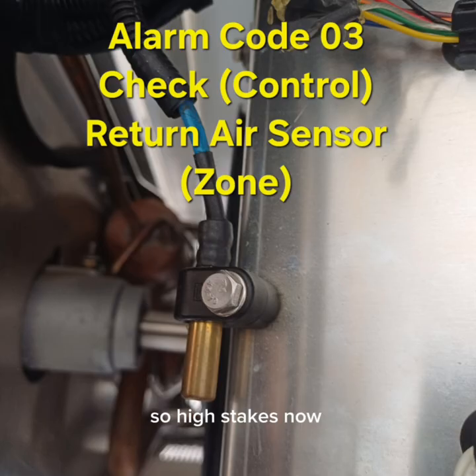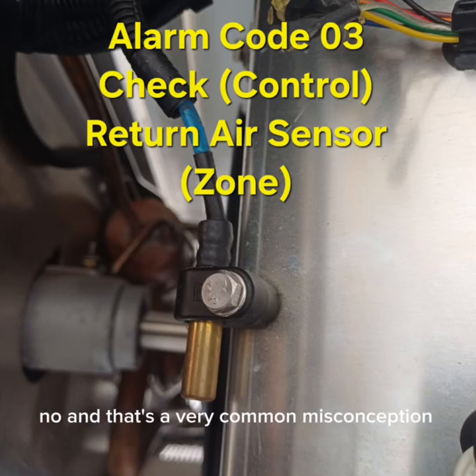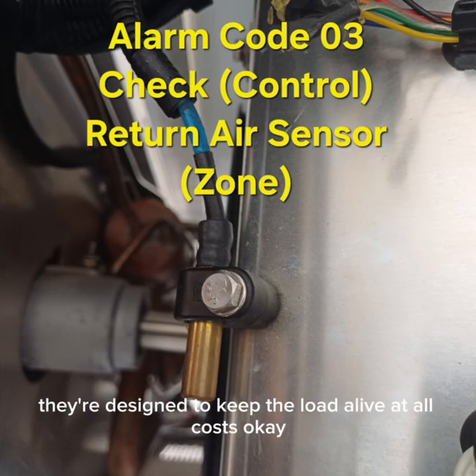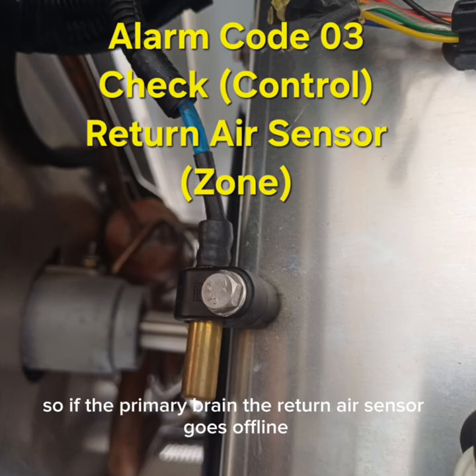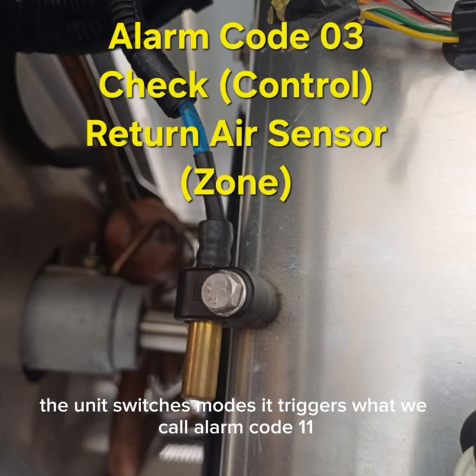Okay, so high stakes. Now, if that sensor fails, if alarm 03 triggers, does the unit just give up? Does it shut down to protect the load? No, and that's a very common misconception. These units are built for survival. They're designed to keep the load alive at all costs. Okay. So if the primary brain, the return air sensor, goes offline, the unit switches modes. It triggers what we call alarm code 11.